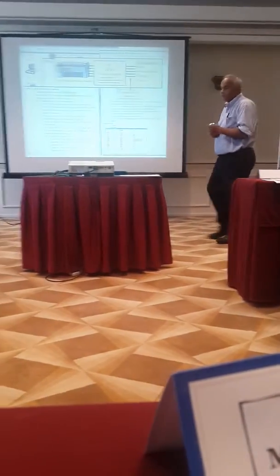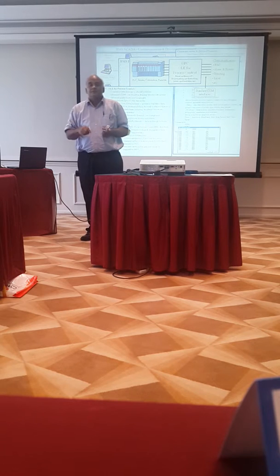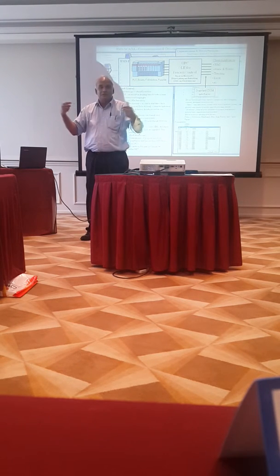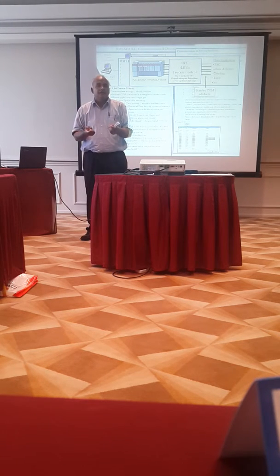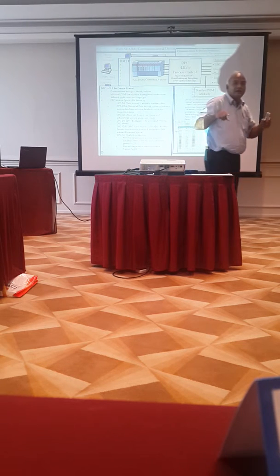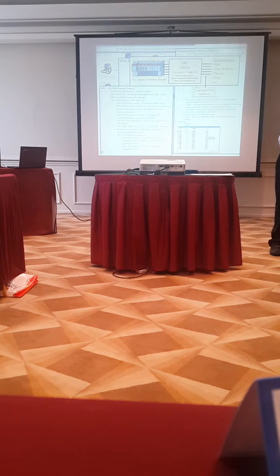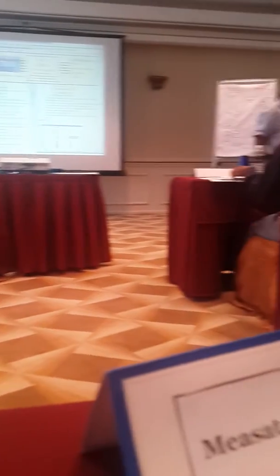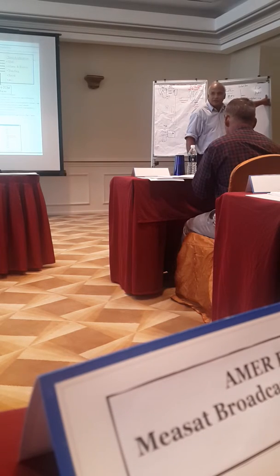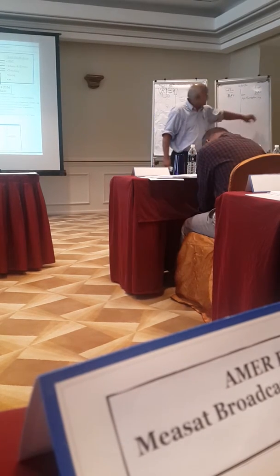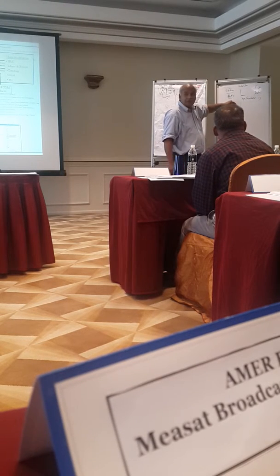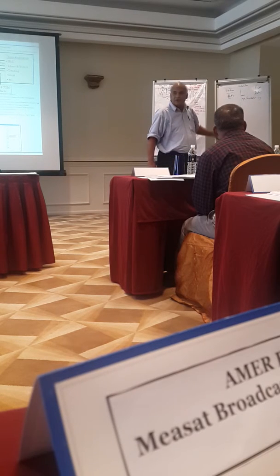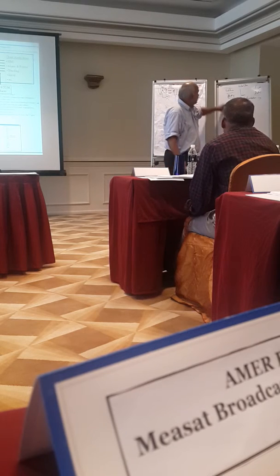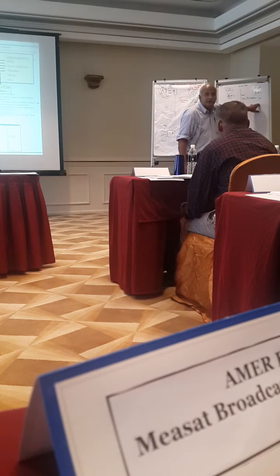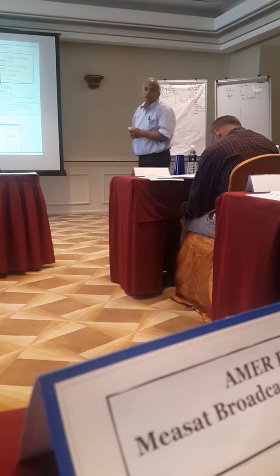Now the advantage of this - remember with Modbus, I said you must do the mapping. The Modbus input is 10001, and you must map it. That is actually very tedious. But yesterday, when I did the HMI software, when I clicked on the button, I could see the variable name in the controller. That is OPC. With OPC, I can actually go into the controller and see the variable name directly, instead of having a variable name here and there that I must map with Modbus to develop my program. Now with OPC, I just take the variable name and link it directly. That's the advantage of OPC.